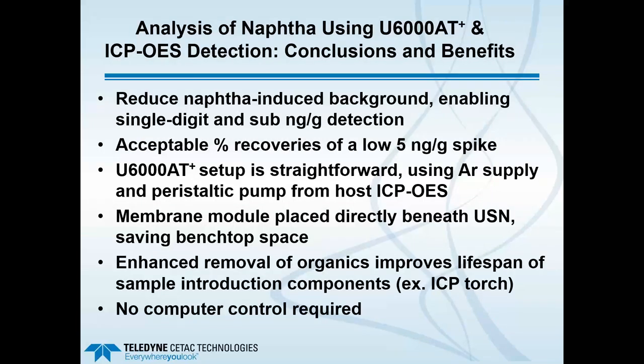In summary, combining the U6000 AT+ ultrasonic nebulizer with the membrane desolvator reduces naphtha-induced background, enabling single-digit and sub-nanogram per gram detection. Acceptable percent recovery was achieved even at a very low 5 ng/g spike. The U6000 AT+ setup is straightforward — using the argon supply and peristaltic pump from the host ICP. The membrane module sits directly beneath the ultrasonic nebulizer to save benchtop space. Enhanced removal of organic solvent improves the lifetime of sample introduction components such as the ICP torch. No computer control or software is required.